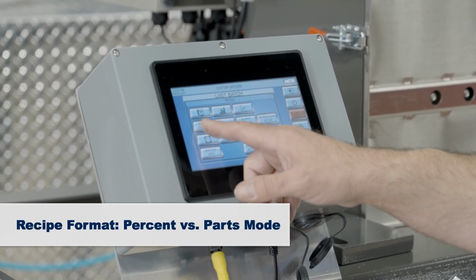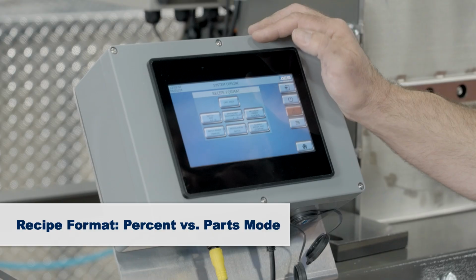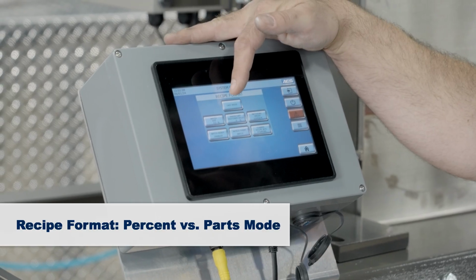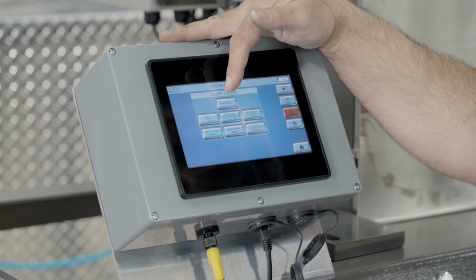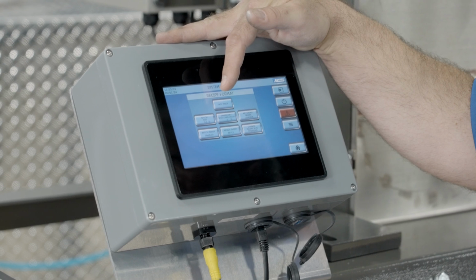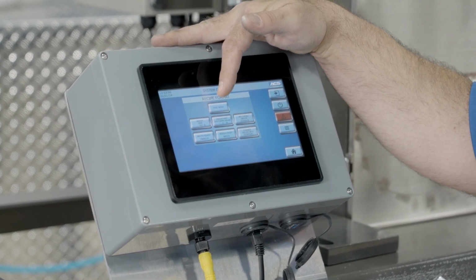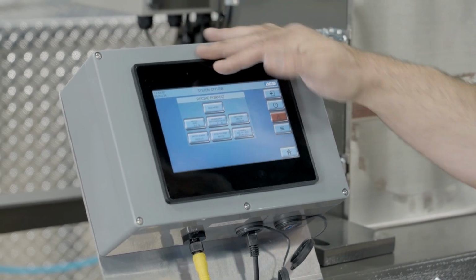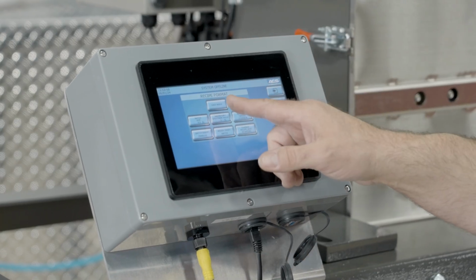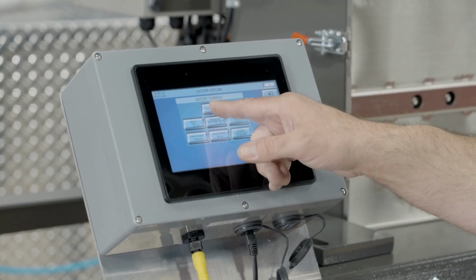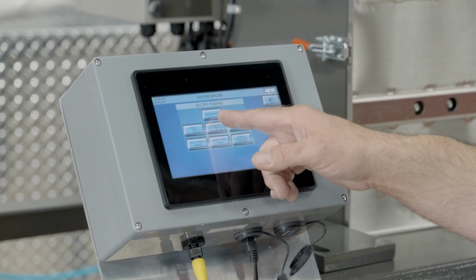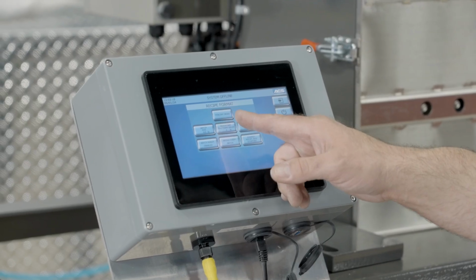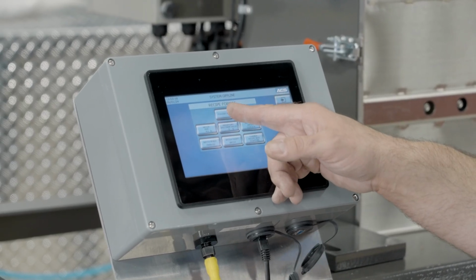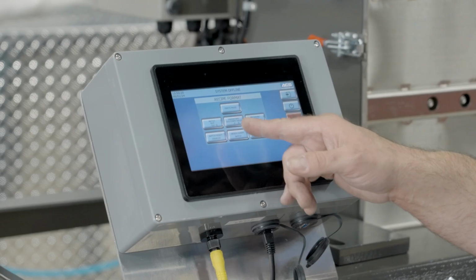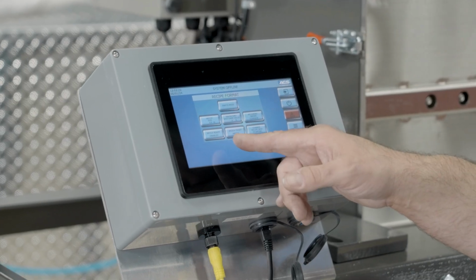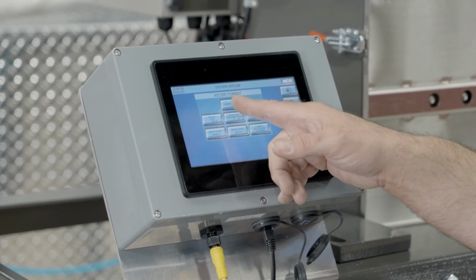Next button is recipe format. All the blenders ship set up in easy recipe mode. This allows the color to be a percentage of your virgin material and your regrind to be a percent of the batch. If you just want to run straight percent mode, if you touch this button, it'll change it to straight percent mode. The next button, there's another format, parts mode. So if you want to enter your recipe in parts instead of percentage, you can do that.